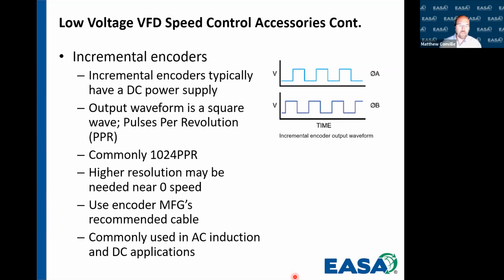One of the things that's a common concern when we use an encoder is that we might get some transients or some harmonics here on this line, on our waveform that is being viewed by the IO card. And that's usually the result of using either improper cable or cable that was not properly terminated. So it's always best to work with the encoder manufacturer to use their recommended cable, and then work with the cable manufacturer to use the appropriate grounding methods or EMI clamping methods. Most commonly, we're going to see incremental encoders being used in AC induction, AC synchronous, AC synchronous reluctance, wound rotor motors, and in DC machines.